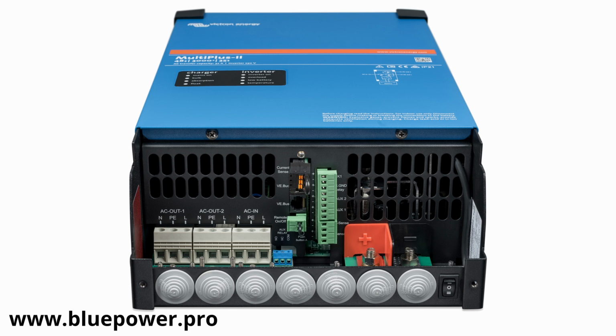So you can't feed 32 amps off the batteries and 32 amps off of your AC input onto output 2. You can, yes. So not 32 amps, but the maximum capacity of the inverter, I'm not sure what the amperage is going to be. That's going to be very close to 32 amps anyway. No? AC out. So it's going to be 12 amps on this one. So you're going to have a maximum 12 amp inverting capability. So that's still going to be limited to your inverter size. Yeah. What you can feed from the batteries. So you can feed 3 kVA from your batteries and 32 amps from Eskom or from your generator to your loads. So it can assist in that way.